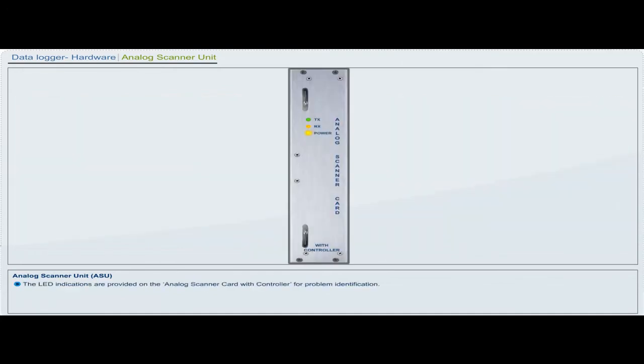The LED indications are provided on the analog scanner card with controller for problem identification. Green LED: TX, data transmission to data logger. Yellow LED: RX, data receiving from data logger. Both TX and RX LEDs should blink continuously if the data is transmitting to the data logger. In case any abnormality is found in the LED indications, please continue further checking.